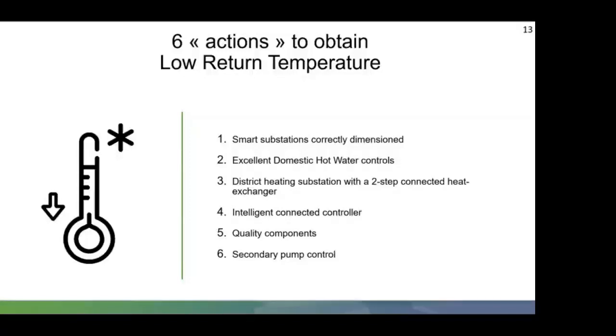The use of high quality components within the substation not only helps with obtaining low return temperatures, but also improves the reliability and gives higher levels of efficiency. By having controls at the secondary circuit pumps, we can maximise the reduction in the secondary return temperatures, which in turn will influence the primary return temperature. By reducing return temperatures, not only will you benefit from savings on the long-term costs, you will also increase the efficiency and reliability of the substation. So again, that substation is not working flat out, it's working at a nice comfortable level.